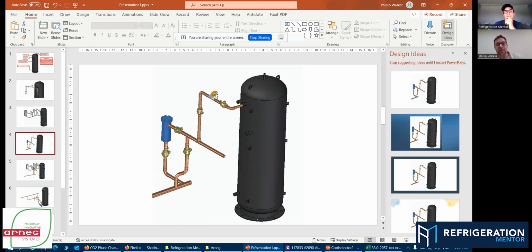And then this valve, if the low temperature needs it, because we don't have a bypass between the two manifolds, like a load bypass, just in case we start losing load, this valve can open more, the mechanical valve, and dump a little more flash gas into the suction manifold of the medium temperature compressors, right? On the medium temperature side for those very small units. But quite the opposite here.